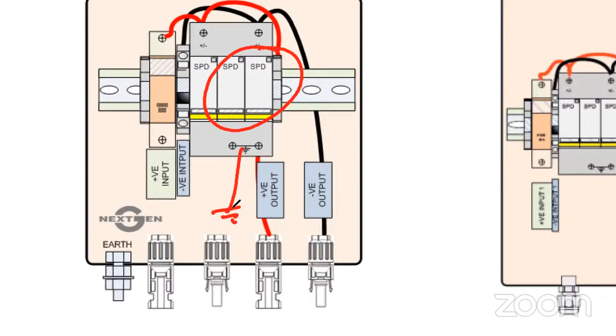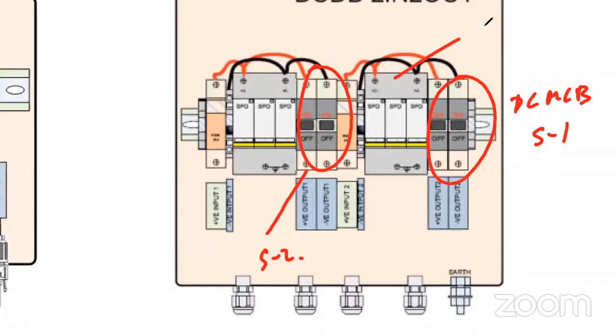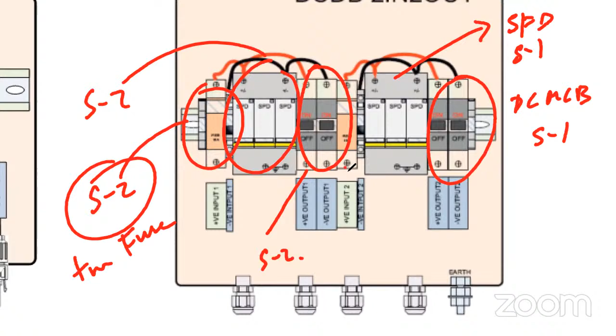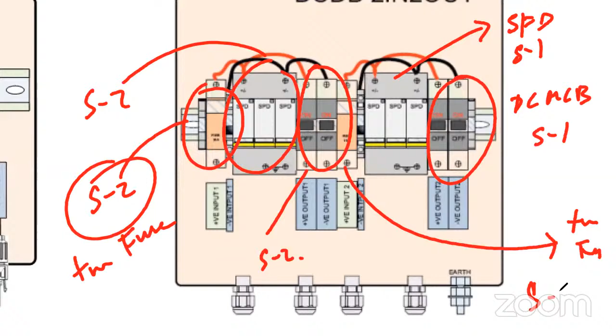Similarly, in this case, this is 2 in, 2 out, so an MCB is there - this is the DC MCB of string 1, and this is the DC MCB of string 2. This is the SPD of string 1, and this is the SPD of string 2. This is the fuse of string 2, the positive fuse. For the negative, they are not using a fuse, but if you want, you can deploy one as an additional safety. Here you can see this is the positive fuse of string 1.